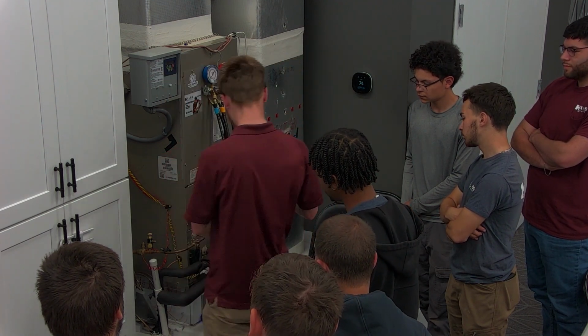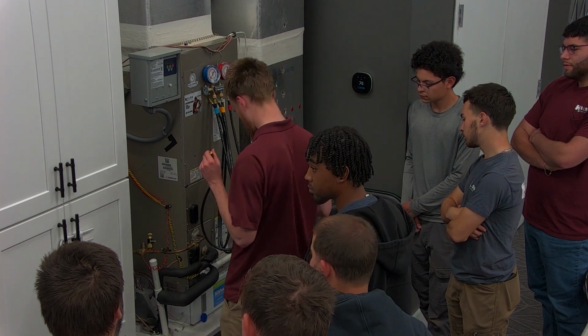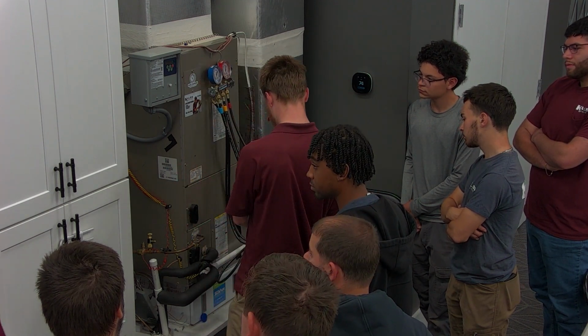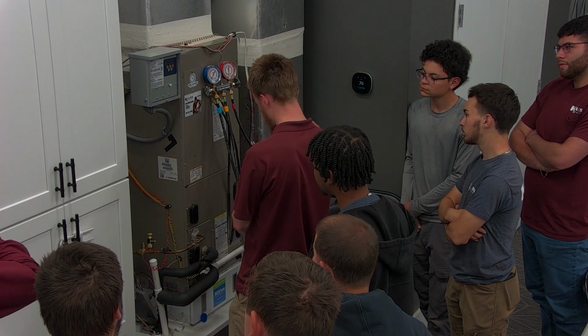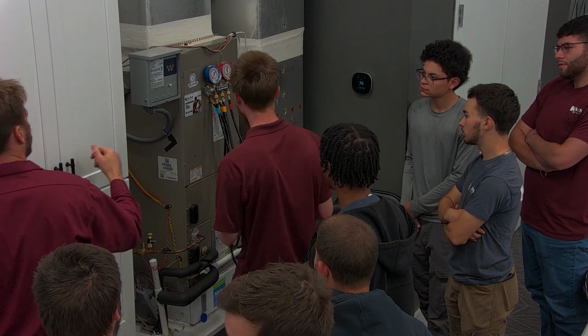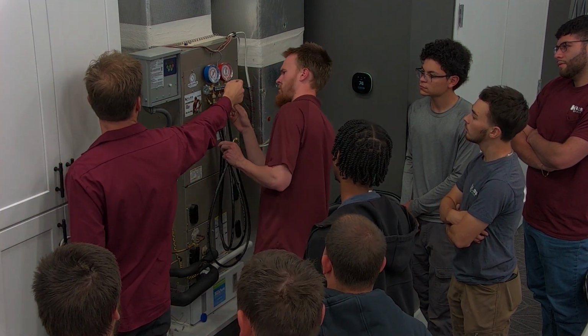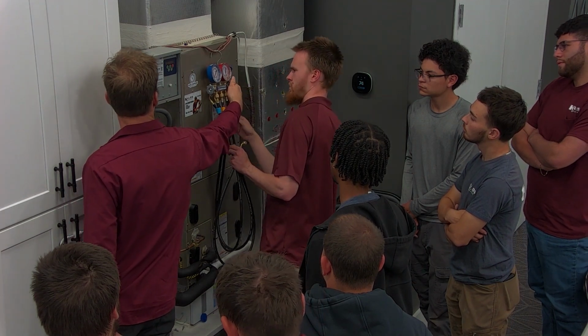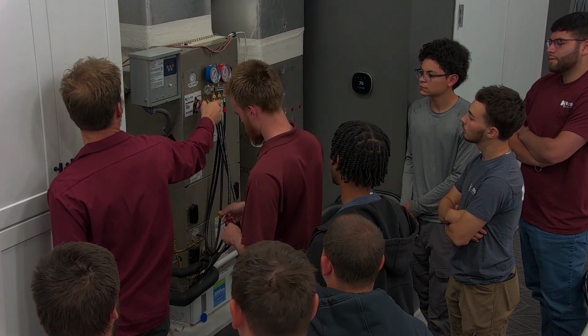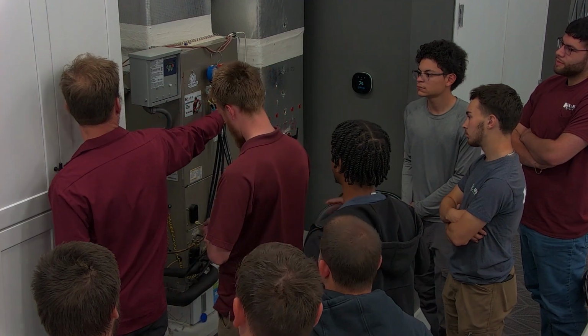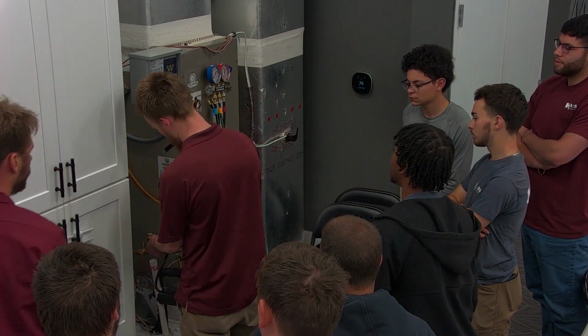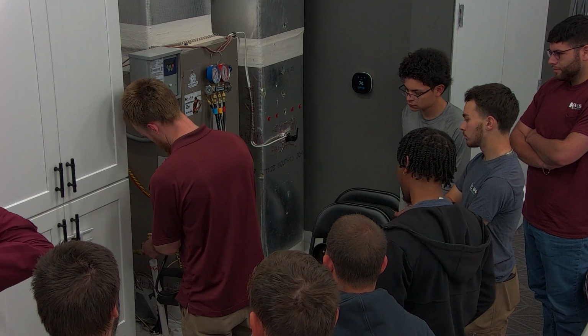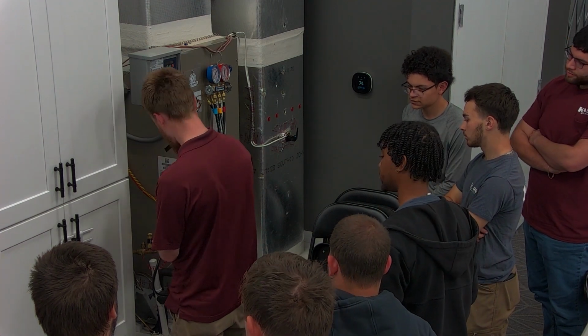Cool. Now, before I ever hook up a manifold gauge to pressure, I make sure my gauge is closed, and at 0, that's good. These are closed, so clockwise is closed. I'm double checking like this. If they're open, as soon as I get pressure, it's going to dump to the other hoses and maybe spray out. Close our gauge. Perfect.